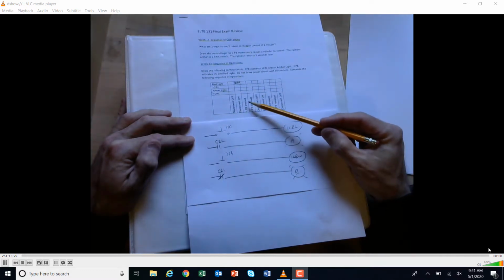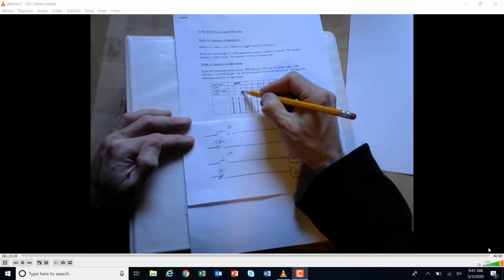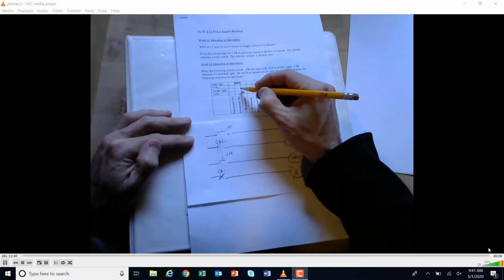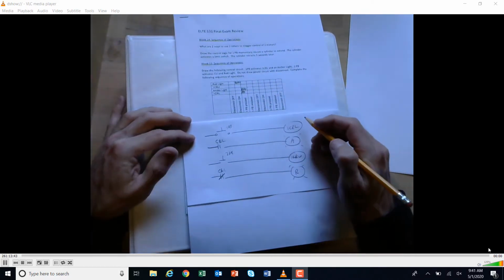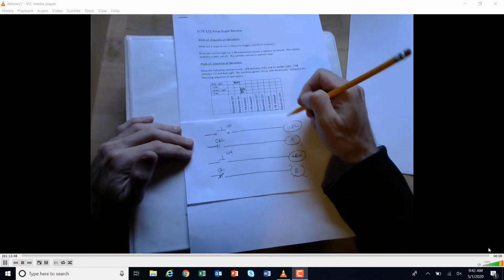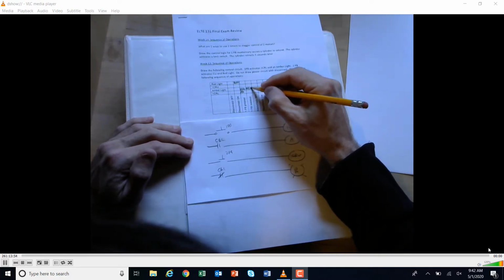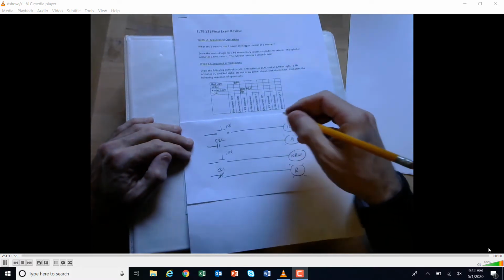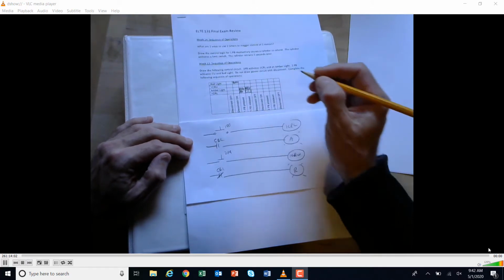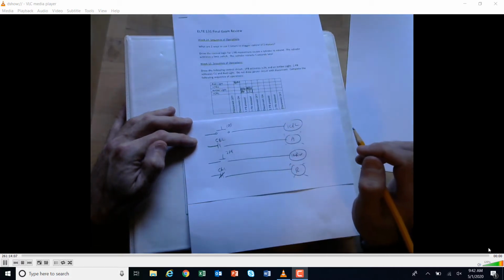Okay, so we could fill that in, probably the red light on. 1 PB is pressed, so while we're pressing it, we get the CRL to come on. The CRL turns on the amber light, and then the red light goes off. We release it because it was latching. The amber light stays on. Now the CRL is not energized, so I'm just going to put a little square on this because it's not energized, but it's still held on, not in an energized state. It's the mechanical latch that held it on.